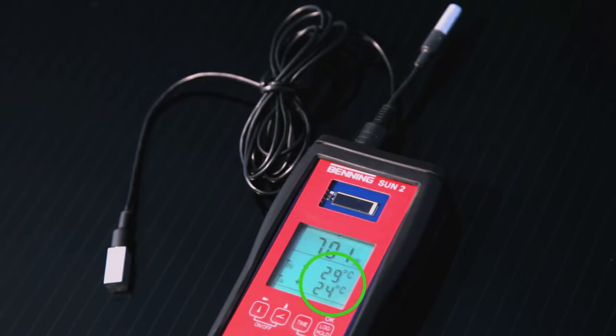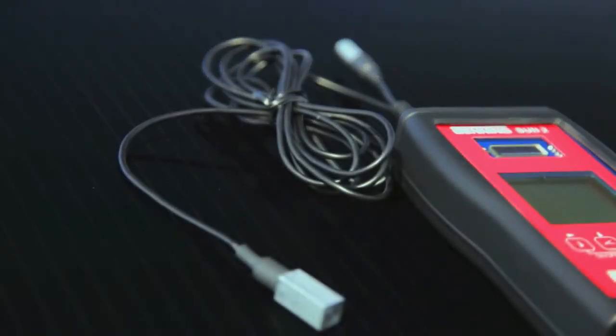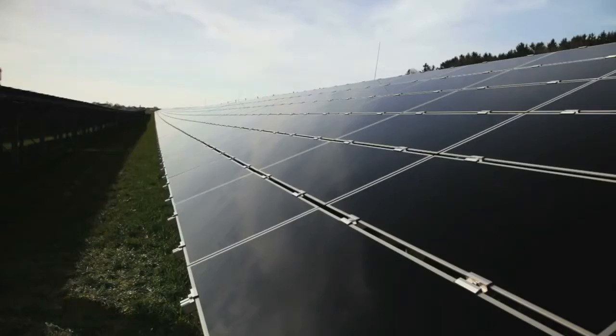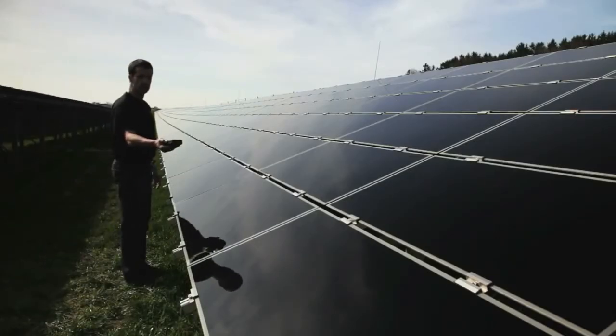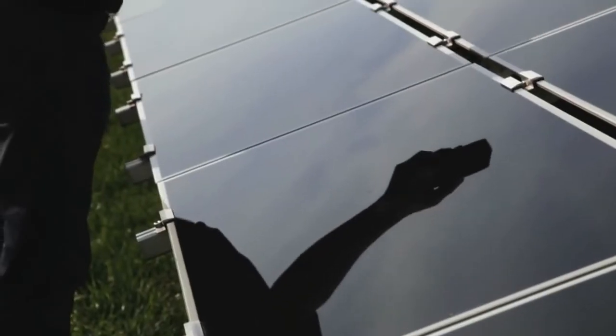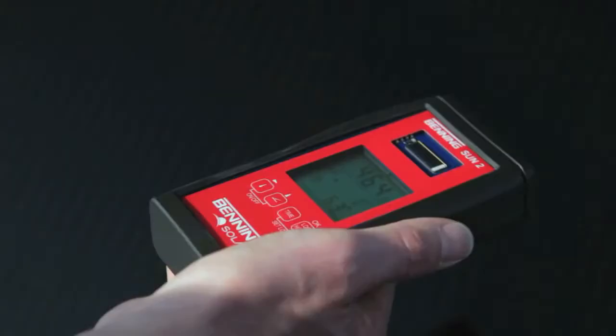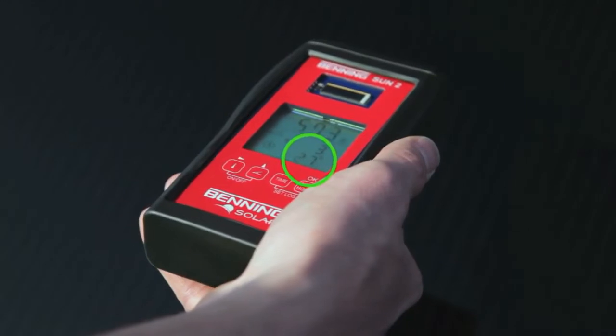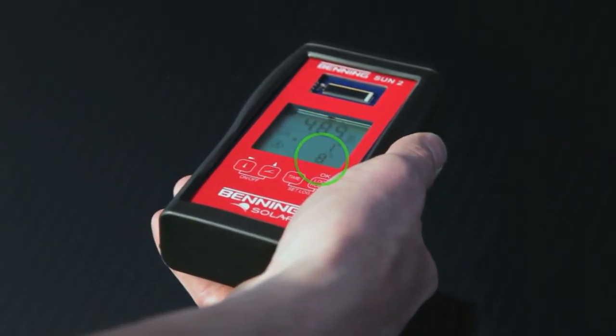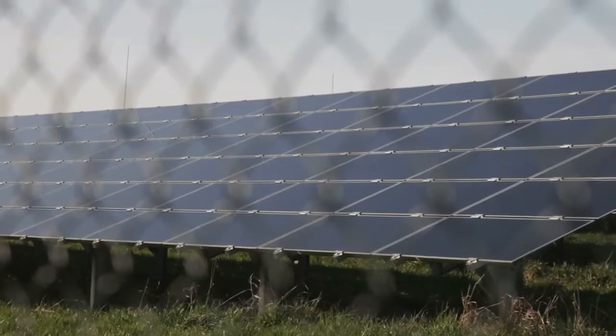The Benning Sun2 measures the insolation via a calibrated PV reference cell and at the same time measures the module and ambient temperature by means of two high-precision sensors. As additional benefit, the Sun2 is equipped both with a digital compass and with a digital inclinometer. The data logger, with real-time clock, can store 5,000 data records in the device.